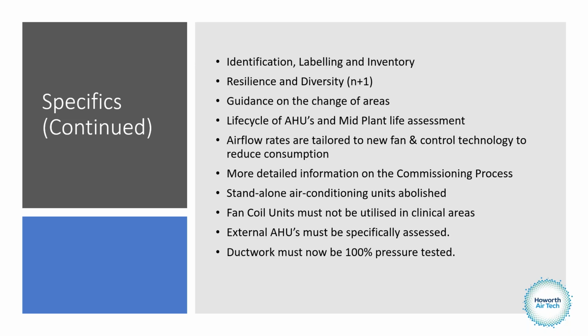Resilience and diversity, N+1, think about it from an electronics point of view. If we have something that goes down, we don't want the space to shut, so we need an N+1 diversity in there. Guidance on the change of areas, life cycle of AHUs and mid-plant life assessment, airflow rates tailored to new fan and control technology. We're not allowed to use belt and pulley fans now, got to be plug fans, EC fans. There's more detailed information on the commissioning process, and standalone air conditioning units are abolished, as are fan coil units from clinical areas. External AHUs must be specifically assessed.